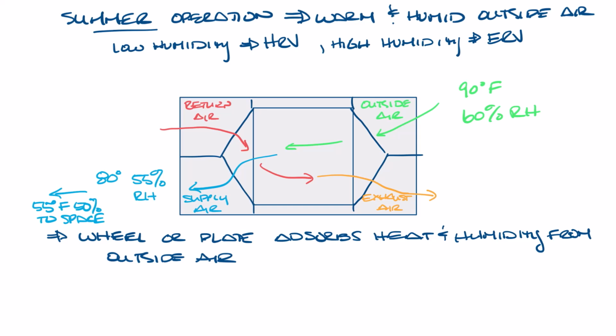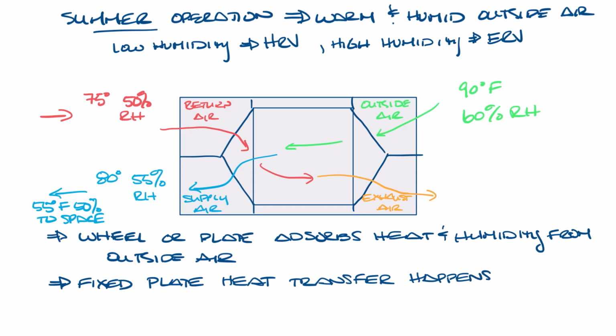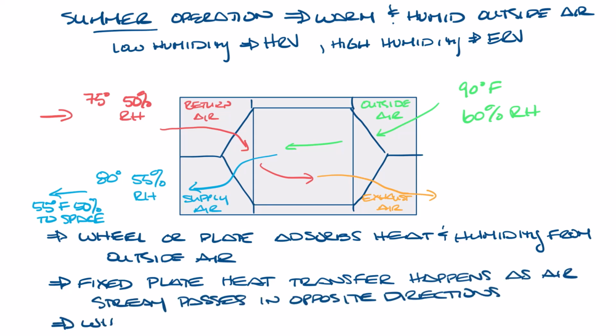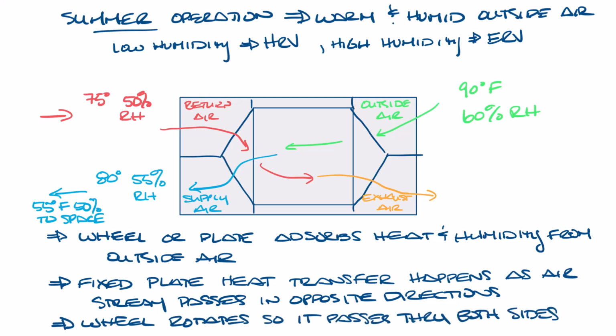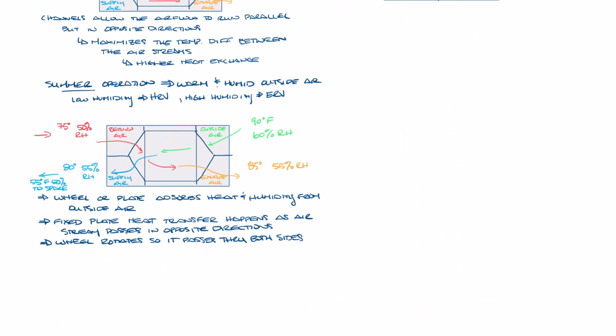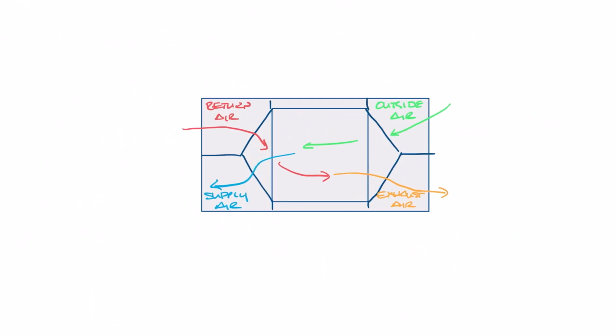Now the return air comes back from the space, say at 75 degrees and 50% humidity, and passes through the wheel or plate channels again. With the fixed plate, the heat and moisture transfer happens as the two airstreams pass through the plate channels. With the wheel design, the wheel is rotating so it passes through both sides of the airstream. The return air passes through the heat exchanger and it's exhausted outside the building at maybe 85 degrees and 55% humidity. Let's make another copy of this and look at the winter operation.